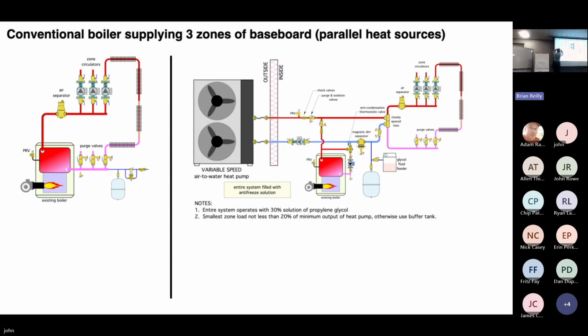So if I can cut it here and cut it here, move the boiler and then reconnect that, you can see I've tied this with a pair of closely spaced tees. Now what this does, again, this is called hydraulic separation. What it does is it prevents these circulators from interacting with these circulators. Again, if we had more time, we could get into it, but it's important when you have multiple circulators in a system that they don't conflict with each other.